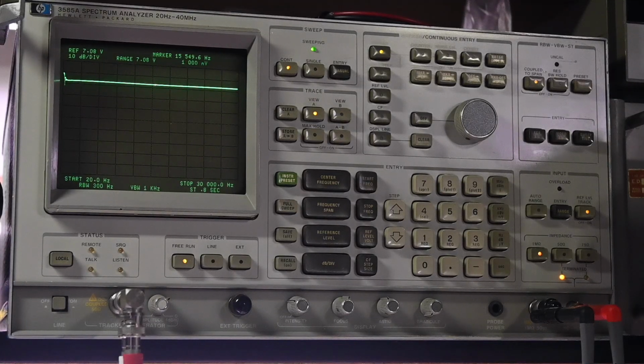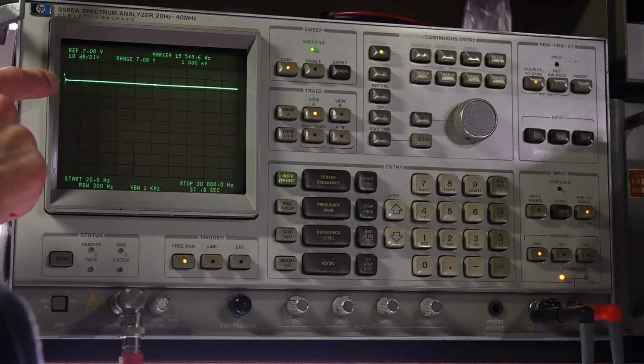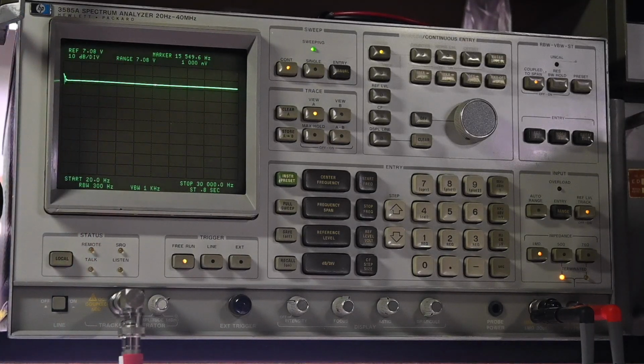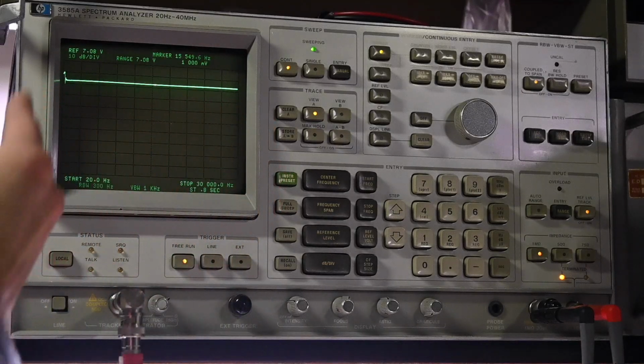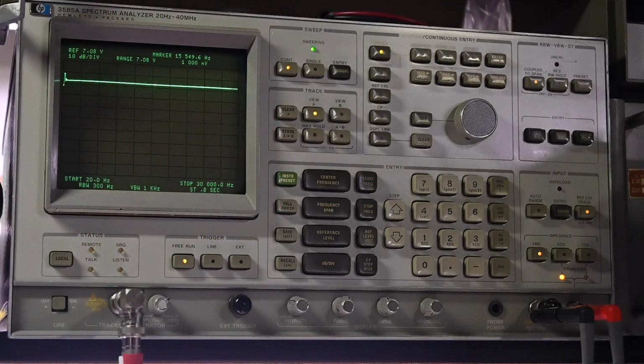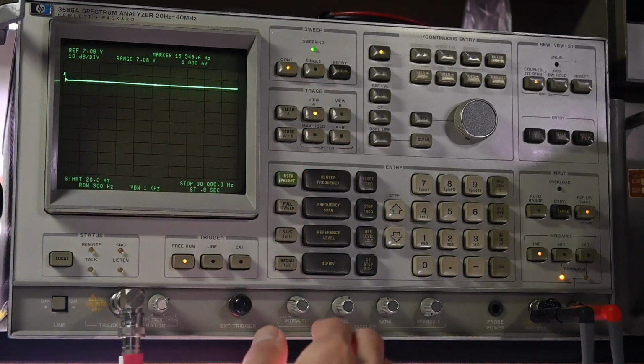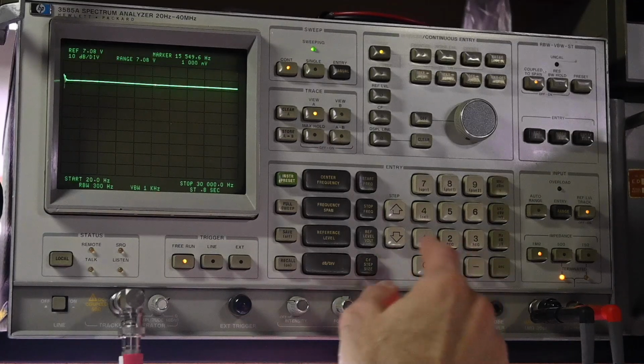Now if I go to the bass control, and I turn the bass all the way up, and I turn the bass all the way down, you can see it just causes a wiggle over here on the end, but it looks like almost nothing's happening. And you might be thinking, well, it's not working correctly. Well, no, because the way audio frequencies work, if it's not a logarithmic scale, then the lowest frequencies are all scrunched over here on the left-hand side. We can change that, but if you can do a logarithmic sweep, that's perfectly fine; this can't do that. So what we need to do is change the stop frequency.